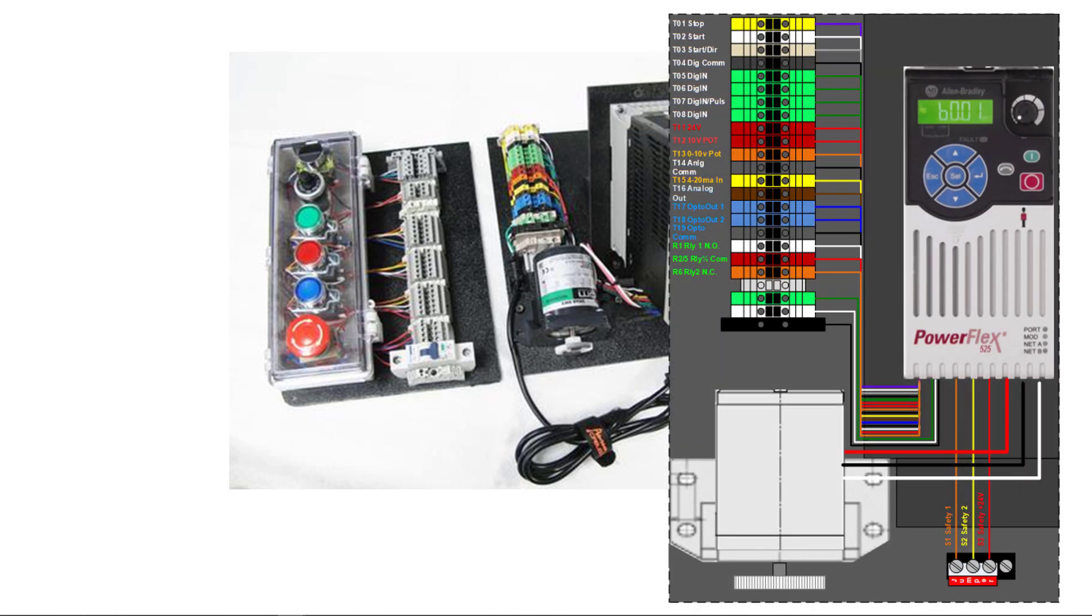If we take a closer look at the drive, you see that we've moved the safe torque off down to a terminal strip down at the bottom next to the motor. And we have our safe torque off with a jumper down there instead of a jumper in the drive. And that's where we will wire in e-stops and other things that we want to control the safe torque off with.